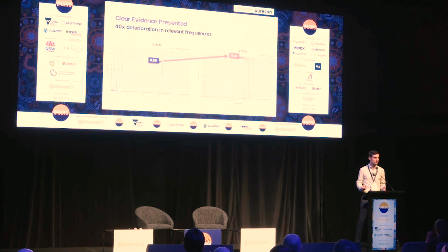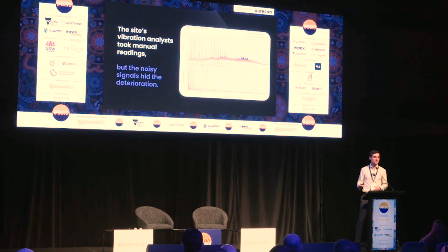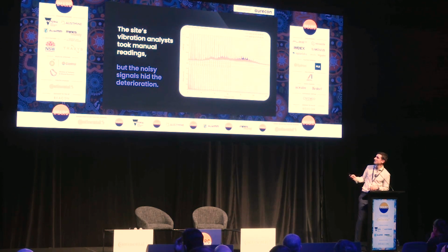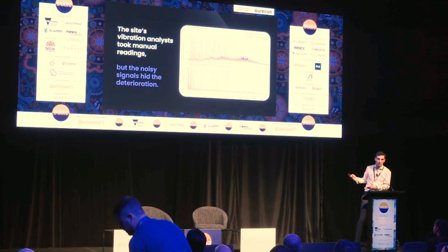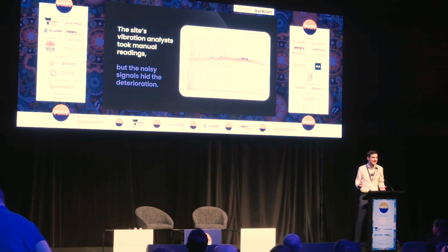The site GM was surprised. They sent their own vibration analyst to take the same readings. That's what they got. Completely noisy data. You try to compare the red to the blue, also one week apart, you don't see anything. So that failure is just completely unseen in the regular information. They took our word for it.